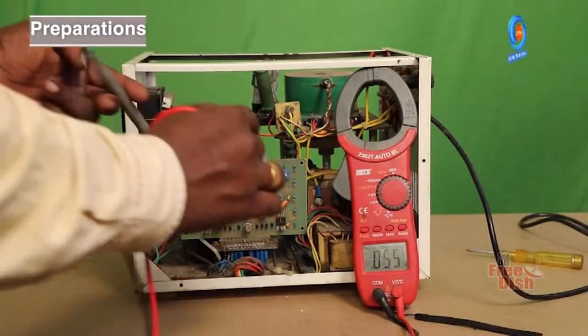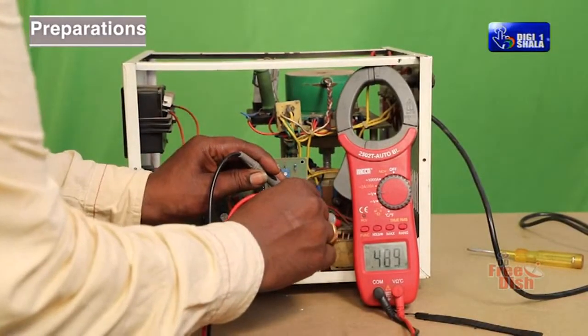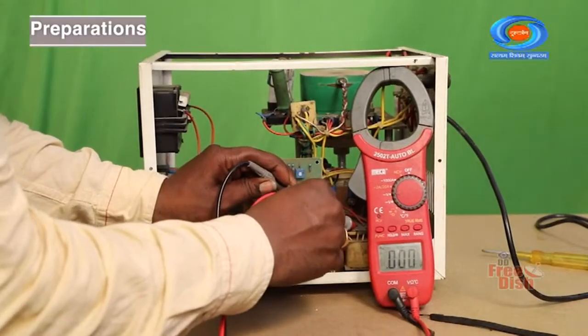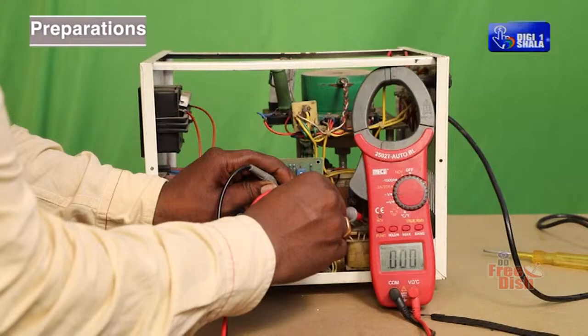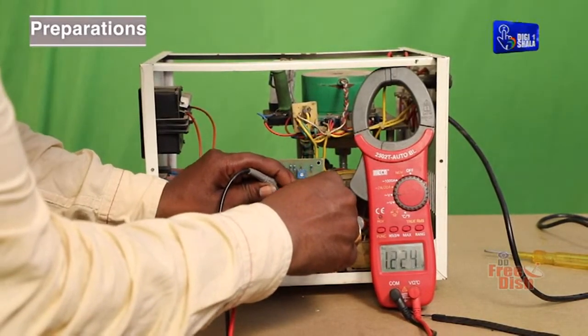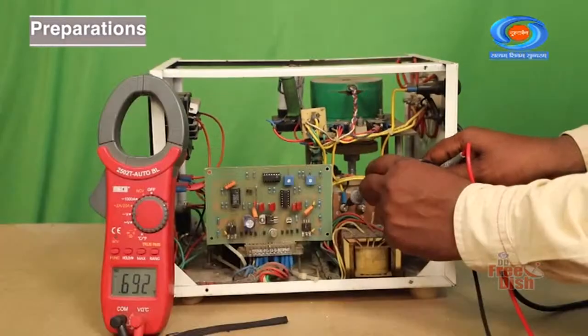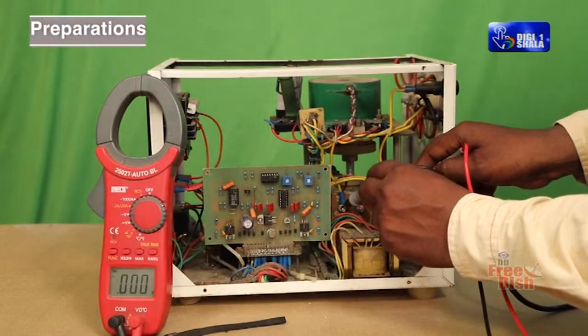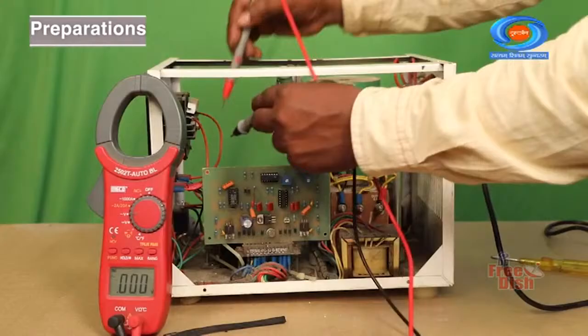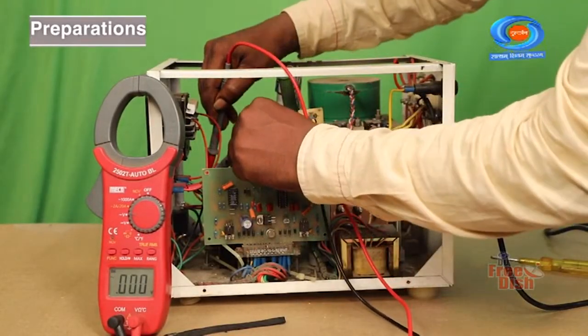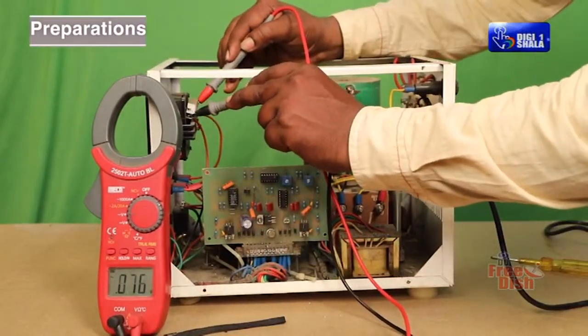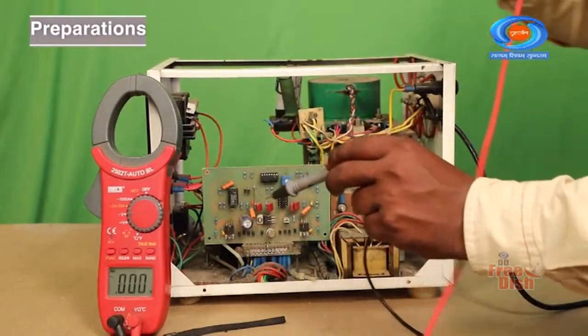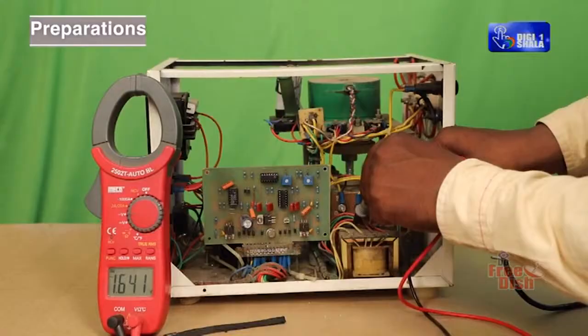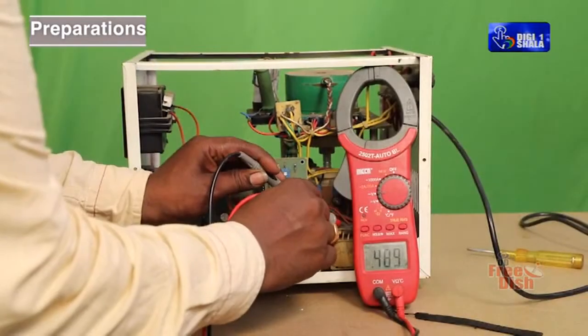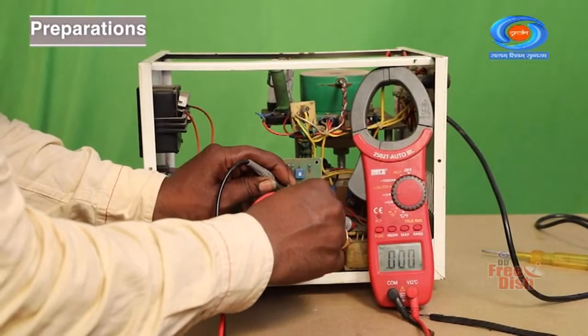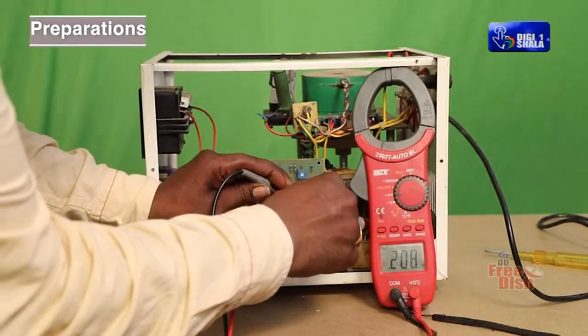Connect the AC main supply cable of the stabilizer unit into the ohm meter and check the resistance by switching on the circuit. If it shows zero resistance, it indicates a dead short. Verify that the input voltage is within the stabilizer's specified range. Check for any open circuit visually or by ohm meter after testing for a short circuit. If the meter shows infinity, that is open circuit.